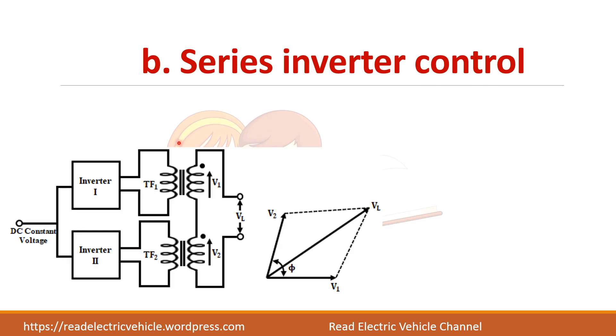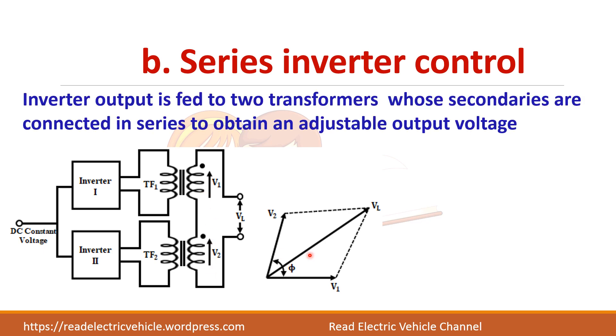The next is the series inverter control method. In this case, the inverter output is connected to a transformer — the primary of the transformer is connected to the inverter output while the secondaries of all the transformers are connected together. The secondary voltages get added — actually it is a phasor addition. You have V1 here and V2 here, and depending upon the phase difference you will get phi. The resultant voltage is VL.